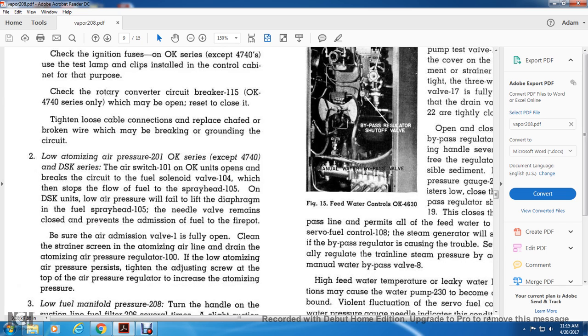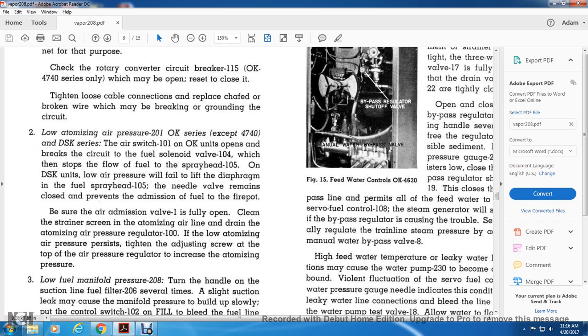Low atomizing air pressure 201, OK series except for 4740 and the DSK series. The air switch 101 of the OK units opens and breaks the circuit to the fuel solenoid valve 104 stops the fuel flow to the spray head 105. On the DSK units, the low air pressure will fail to lift the diaphragm and the fuel spray head 105. The needle valve remains closed, preventing the admission of fuel into the fire pot. Be sure the air admission valve is fully open. Clean the strainer screen, the atomizing line, and the atomizing air pressure regulator 100. If the low atomizing air pressure persists, tighten the adjusting screw at the top of the air pressure regulator to increase the atomizing pressure.